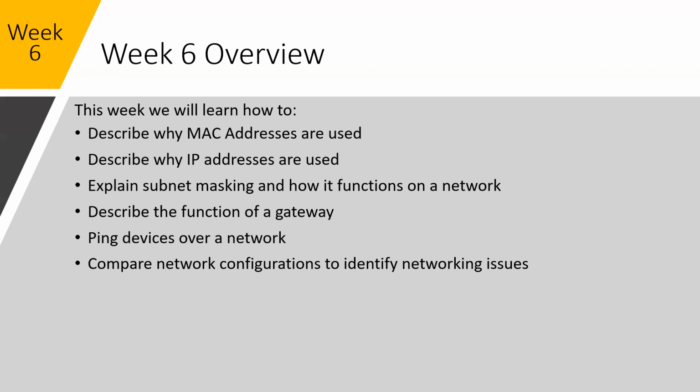Yeah, if you walk into a manufacturing facility and you just plug your laptop into a switch, and your computer takes the same IP address as a piece of equipment on the network, you can bring the whole thing down if you take out the wrong piece of equipment. If you come on and you take over a VFD that's being controlled over Ethernet, the whole thing will stop. You can fault controllers. So there are some basic tools that you can use to help prevent that.